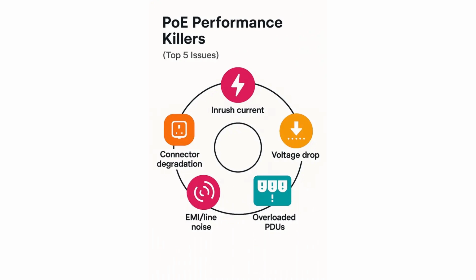That's when you start to look at other types of low voltage DC systems that can power those things but can peak higher than 100 watts. Another limitation is the distance limitation of 325 feet from your endpoint. So you have to consider that when you're laying out your infrastructure: how far away is your device, how far away can I be from them? Those are the two main limitations. It's the power and the distance. Got it.